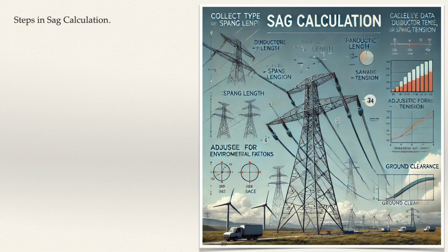Steps in sag calculation. 1. Collect required data: conductor type, weight and elasticity, span length and tower spacing, environmental conditions, e.g. temperature, wind, and ice loading, clearance requirements, e.g. ground, road, or river crossings. 2. Determine conductor tension. Calculate the tension needed to maintain structural integrity and meet clearance requirements. 3. Apply sag formula. Use the parabolic or catenary method based on the span length. 4. Adjust for environmental conditions. Account for temperature expansion, ice loading, and wind forces to ensure sag remains within safe limits under all conditions. 5. Verify against standards. Check calculated sag against regulatory clearance requirements and safety standards.